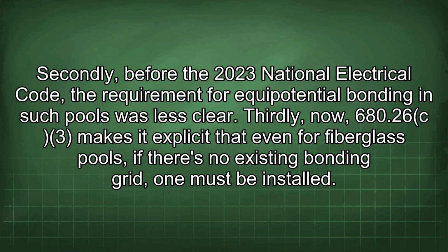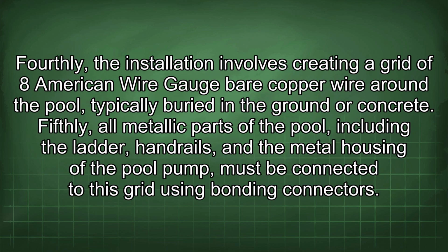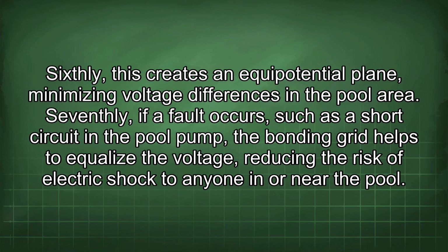Thirdly, now, 680.26(c)(3) makes it explicit that, even for fiberglass pools, if there's no existing bonding grid, one must be installed. Fourthly, the installation involves creating a grid of 8 American wire gauge bare copper wire around the pool, typically buried in the ground or concrete. Fifthly, all metallic parts of the pool, including the ladder, handrails, and the metal housing of the pool pump, must be connected to this grid using bonding connectors. Sixthly, this creates an equipotential plane, minimizing voltage differences in the pool area.